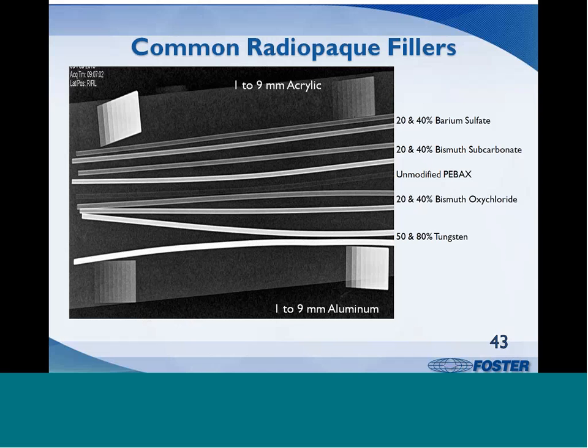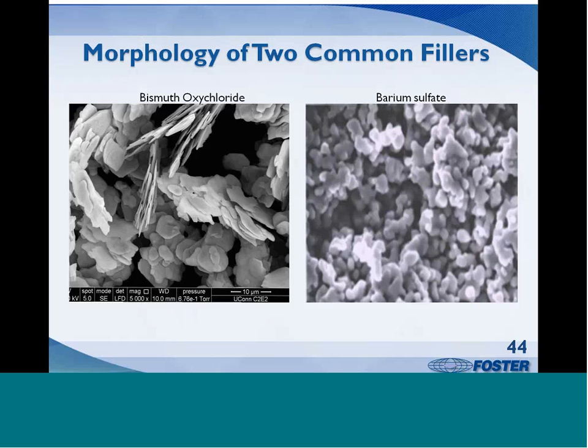In this case, 20% barium sulfate is equivalent to 1 millimeter of aluminum, and 80% tungsten is more effective than 9 millimeters of aluminum. The fillers come in several morphologies. Most are small, irregular particles made by milling larger particles, and that would be representative of the barium sulfate. Bismuth oxychloride is unique with its plate-like structure, which gives rise to a level of pearlescent effect in the final part.